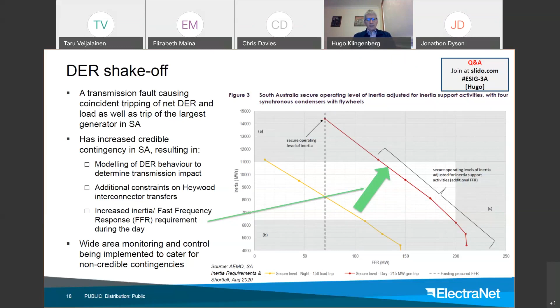The last slide I want to focus on is just looking at what this means for managing the interface between transmission and distribution. In South Australia, we've got about 40 of these connection points, and where we are two weekends ago, half of those were in reverse power flow, meaning that the transmission network is absorbing energy coming in from the distribution network, which is completely different to the original design of a one-directional flow from transmission into distribution down to the low voltage.